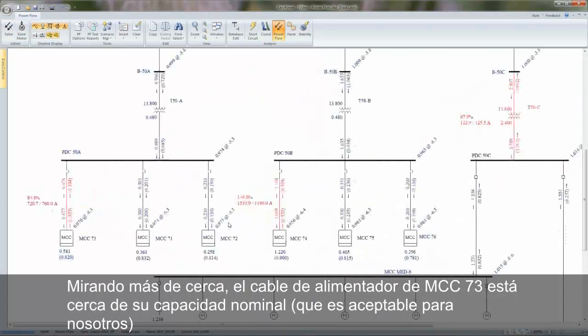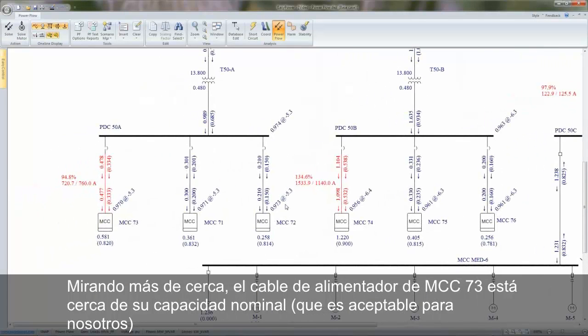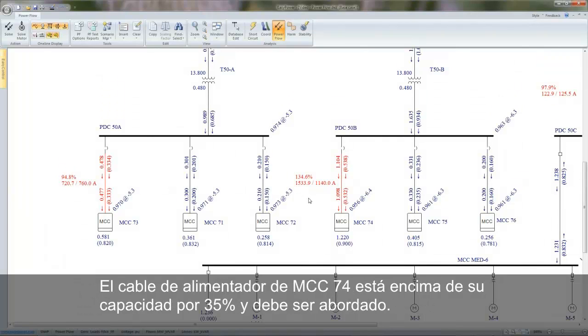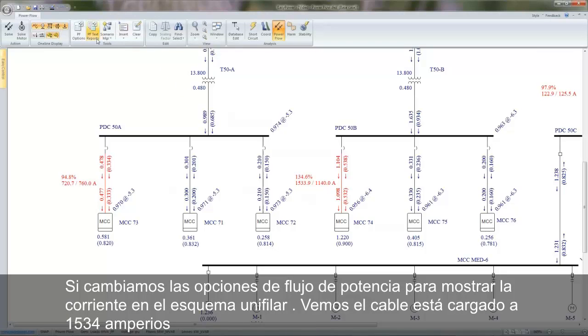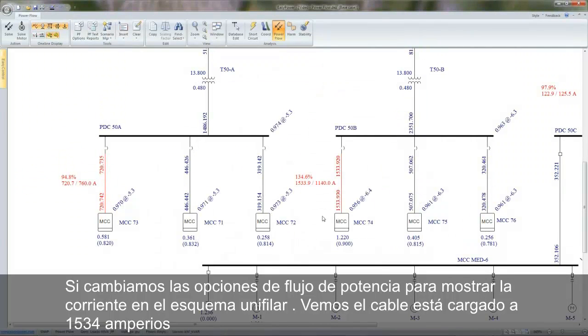Looking more closely, we see the cable feeding MCC 73 is near its rating, which is acceptable to us. The cable feeding MCC 74 is over its rating by about 35% and needs to be addressed. If we change the power flow options to showing current in amps, we can see that the cable feeding this MCC is loaded to 1534 amps.